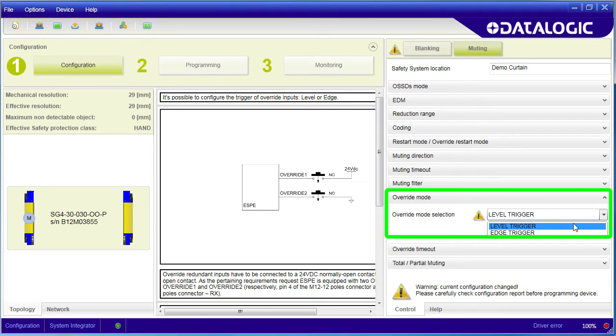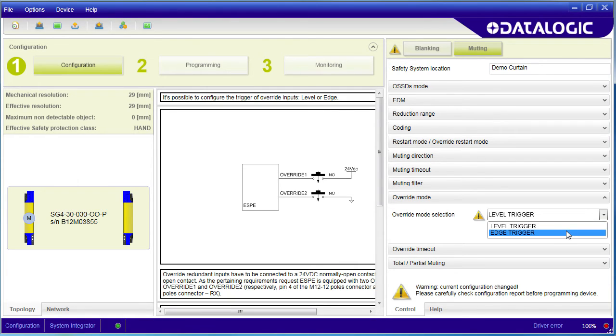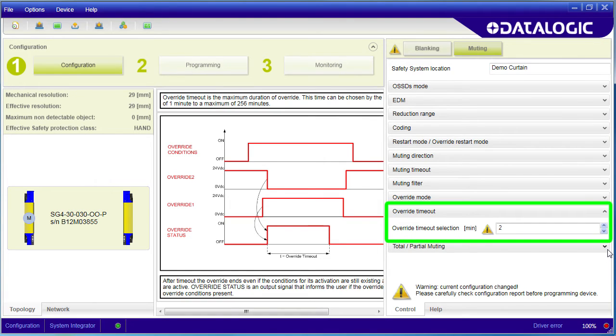You would want level triggered if you want someone to literally hold a momentary button down. If you want just a momentary button pressed to enable muting so you can walk away, then you would use this one. And you can specify a time out for the Override too.